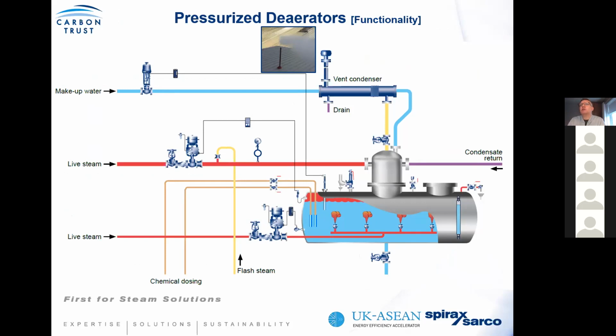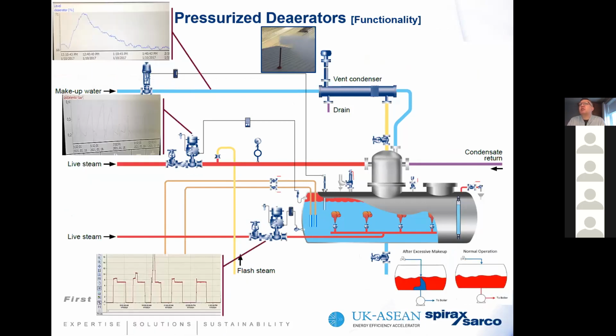of a package solution. What we're suggesting as a first is for your own process, understand. So look at your level controller. Are you seeing that your level is not constant? Are you seeing that your level is very periodic? You're adding water, on-off control. Look at your pressure on your deaerator. Do you find that the pressure swings up and down? Do you find that the amount of steam that's coming from your vent pipe could be very violent and quite significant, and then drop off quite significantly, sometimes to nothing?